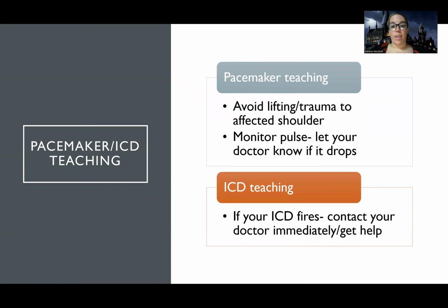So what teaching do we want to give about these? There's a whole lot of stuff in your book, but here are the takeaways. I want to leave this out here because there are a lot of misconceptions: yes, you can use a microwave with your pacemaker and ICD. They are microwave safe. When it comes to MRIs, it's touch and go. In real life today, most of them are MRI safe, but we usually have to follow a protocol, call the company, and verify it.